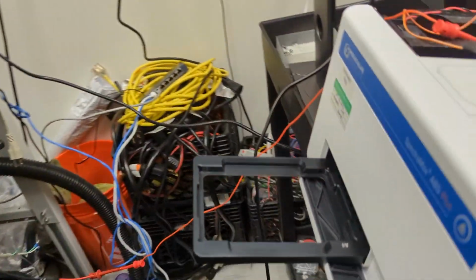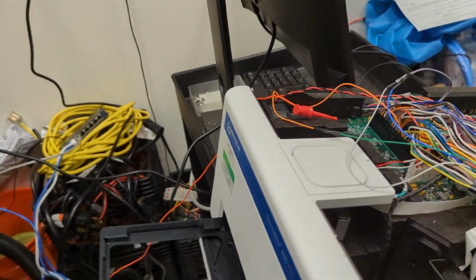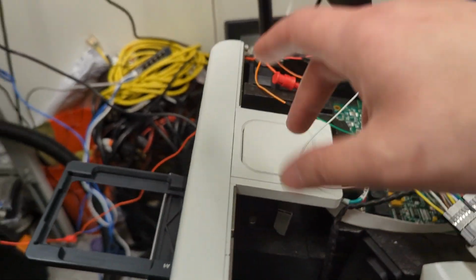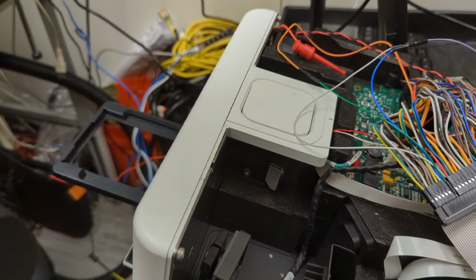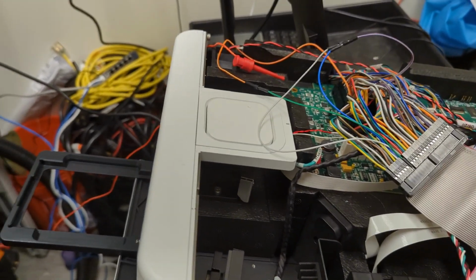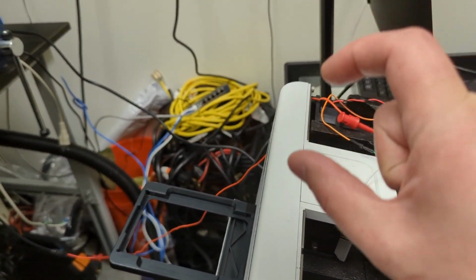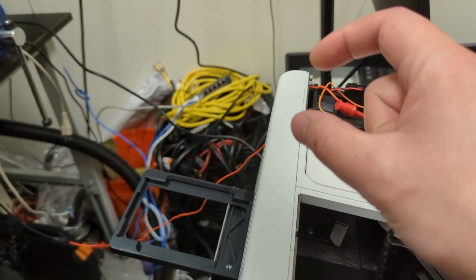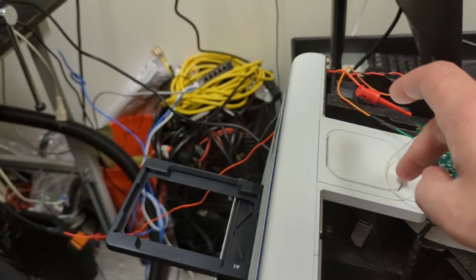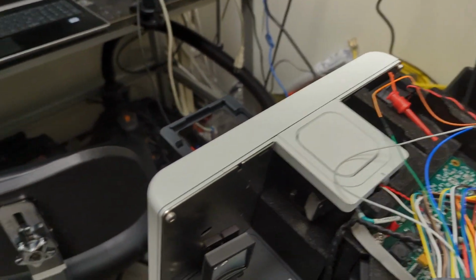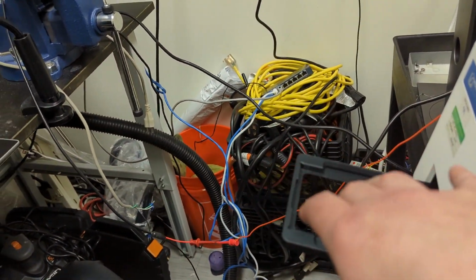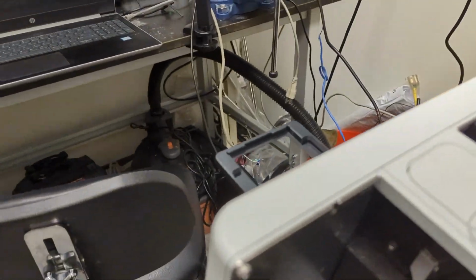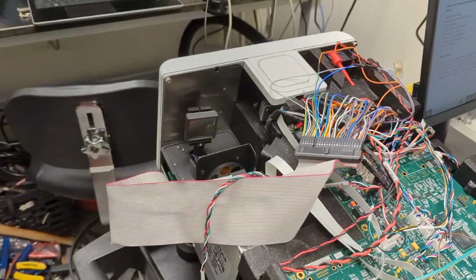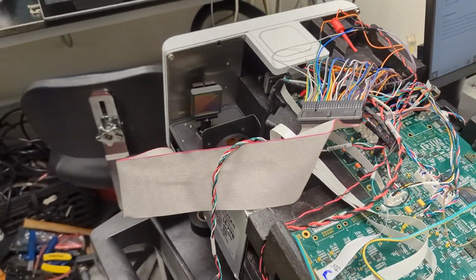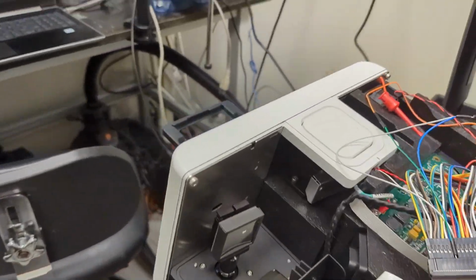And so you can put these on this instrument. This is the plate carriage that they go on, and the instrument will analyze all of those wells. There is a cuvette reader chamber here as well. So if you are familiar with spectroscopy, you've probably heard of the cuvette, which is just a small piece of quartz, a holder basically where you put your sample in, and so it has that as well. Most people are familiar with those, and not so much a plate like I just showed you. But anyway, that's what this thing does, and it measures absorbance. And I can go into a little bit of detail about how these things work. They're all very similar, but I've got the thing open, so I figured I'd show you.